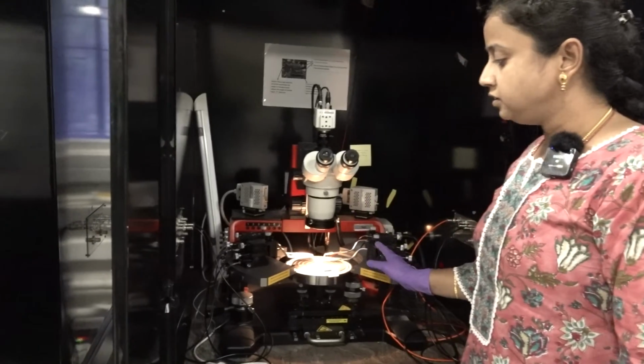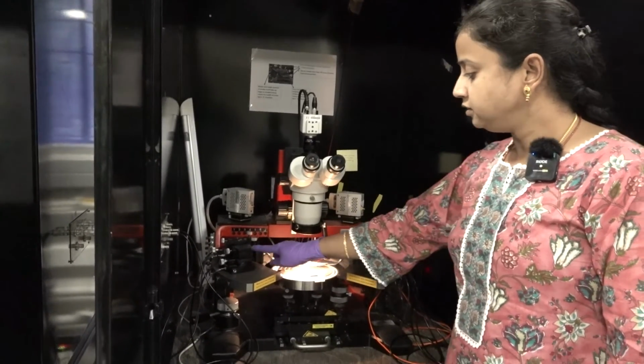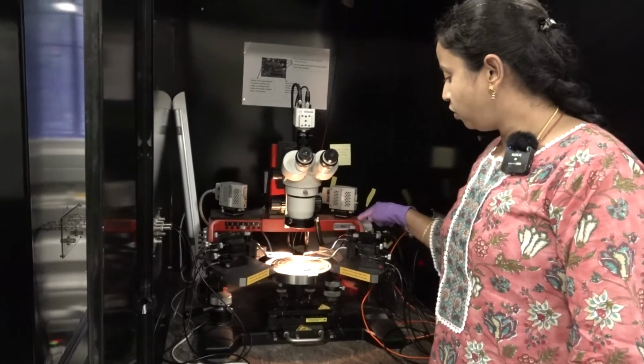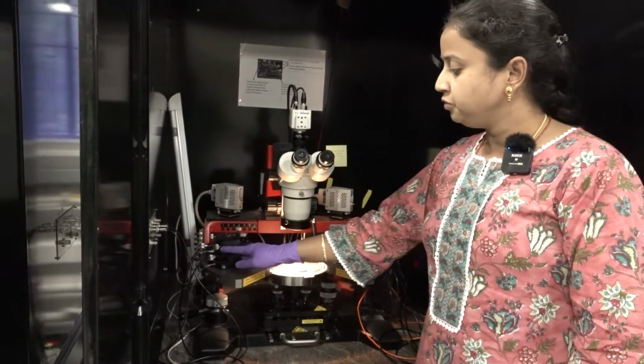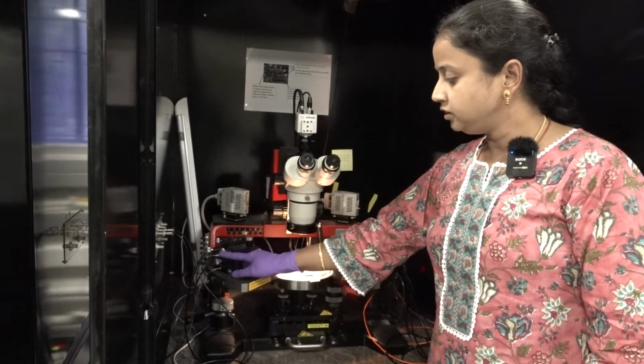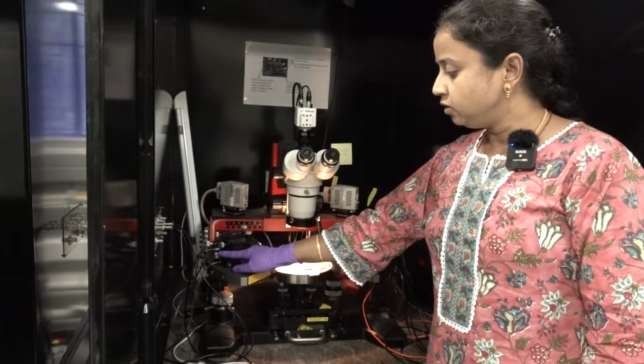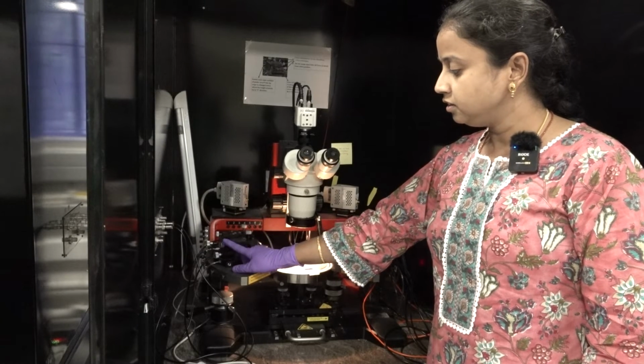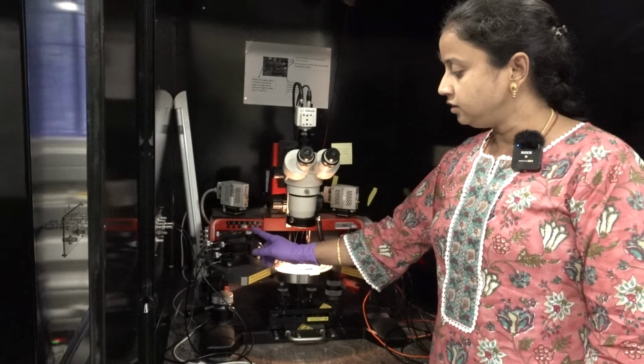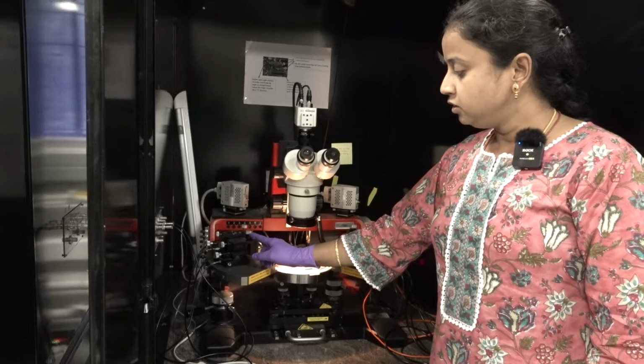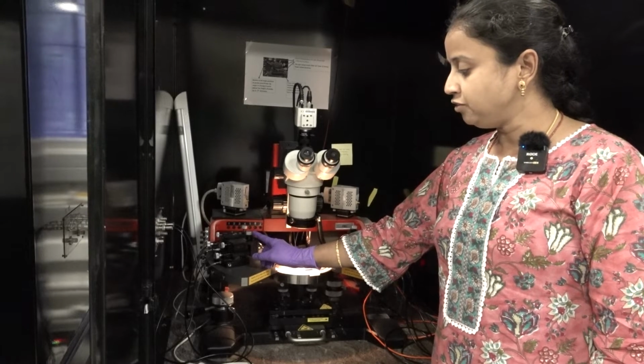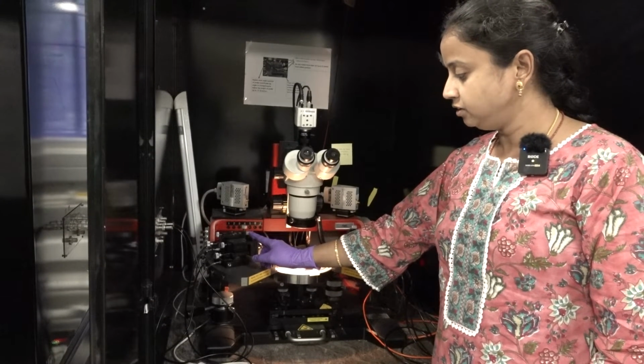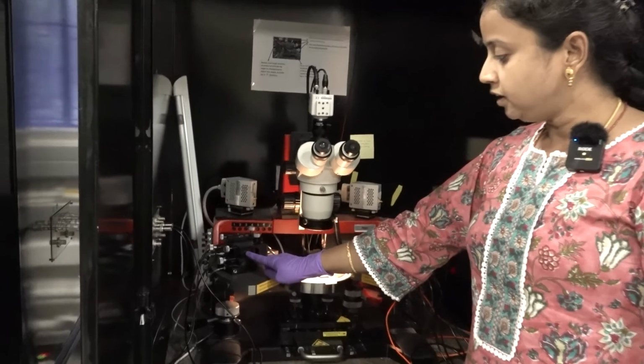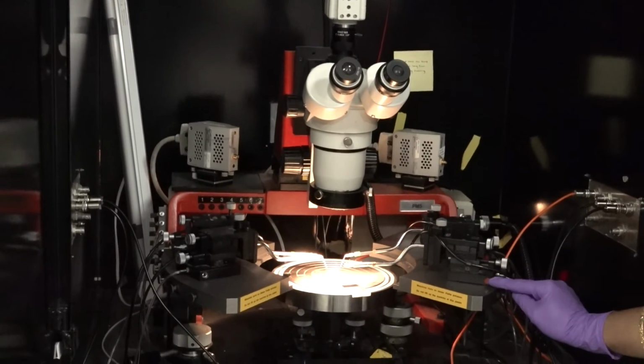So the probe station consists of 4 manipulators. So these are 4 manipulators. So we have some positioners. So these are called as positioners. So this is the X positioner, this is the Y positioner and this is the Z positioner. The rotation for this positioner is 150 micron per rotation. So this manipulator also has a vacuum here.